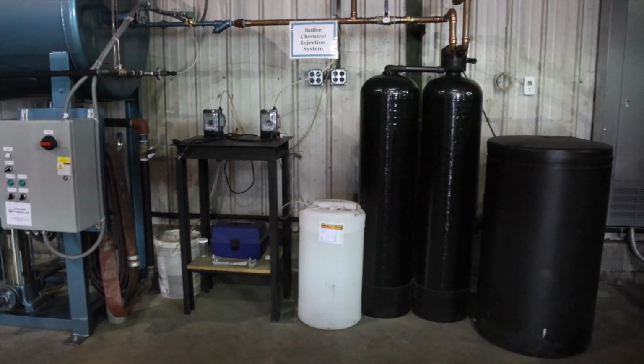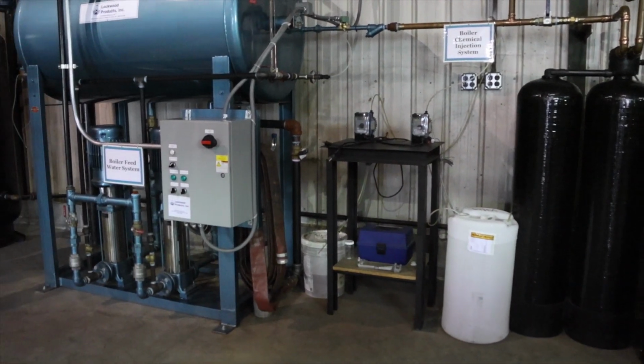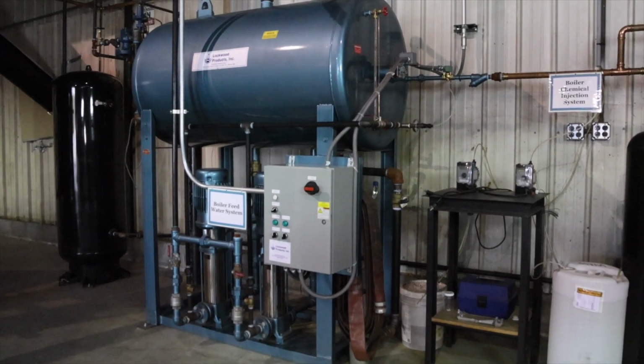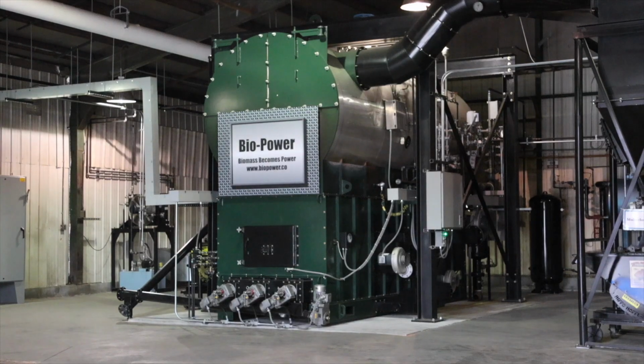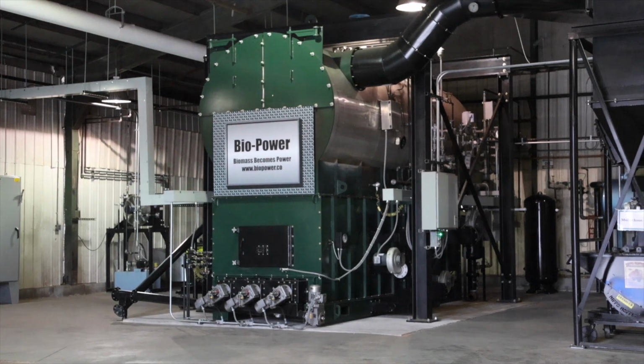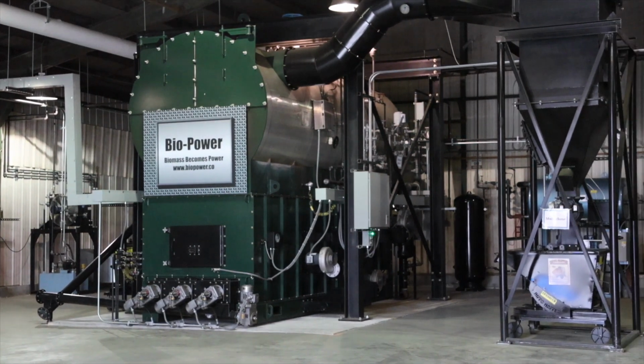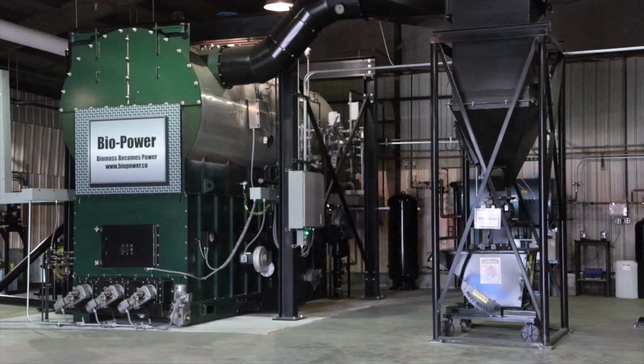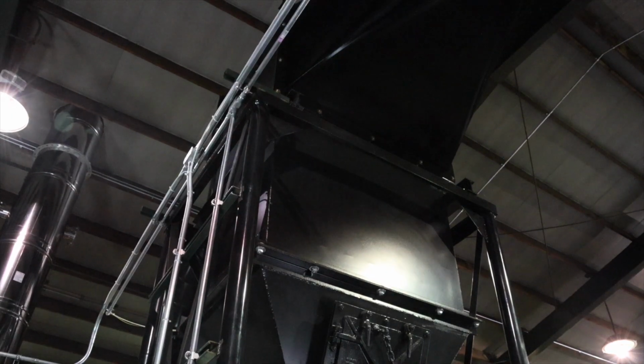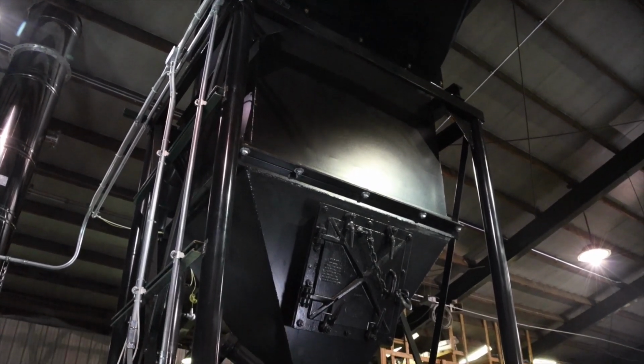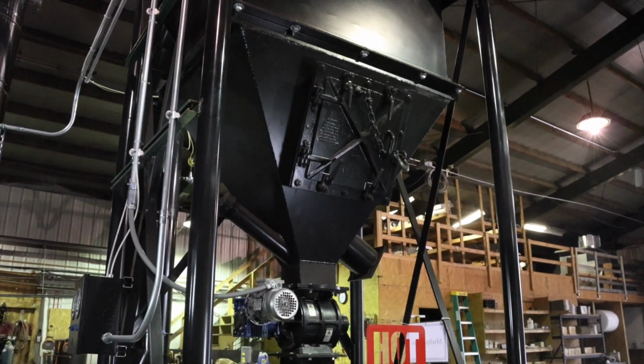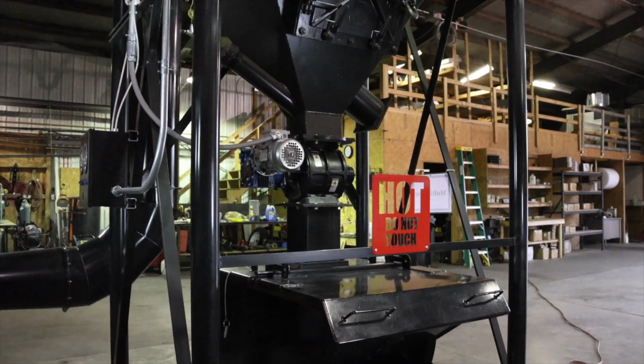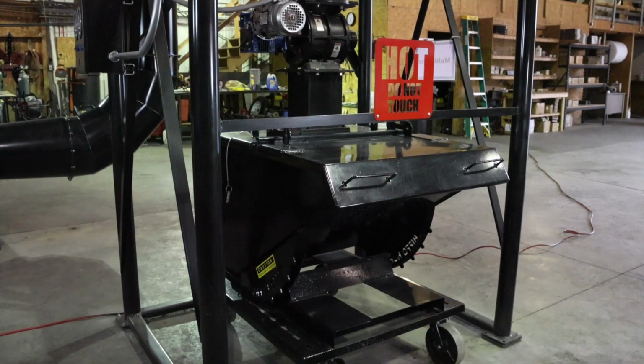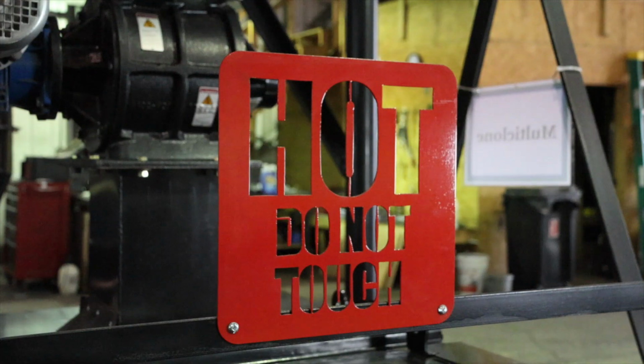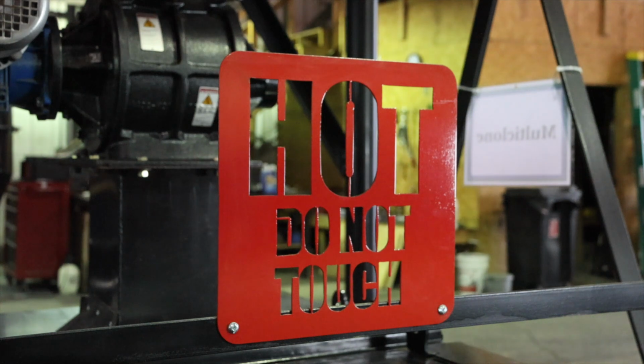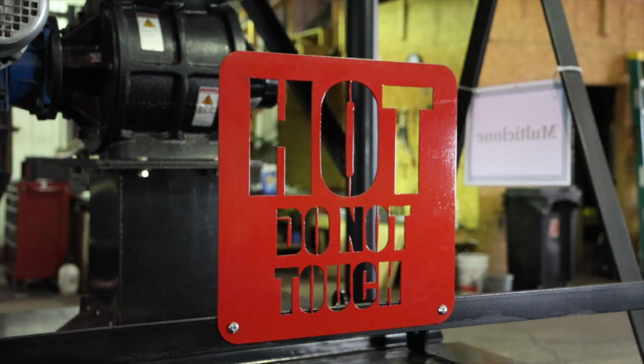Providing the feed water to the boiler is our boiler feed water system, and water quality is maintained through a chemical injection system. After the combustion gases pass through the boiler and the energy has been extracted to make steam, the gases exit the boiler through ductwork and enter the multiclone. The multiclone is an emissions control device used to remove most fly ash from the combustion gas stream, preventing the ash from exiting out the stack and entering the atmosphere. The fly ash is separated and passes through a rotary airlock and into an ash bin, which is periodically emptied.